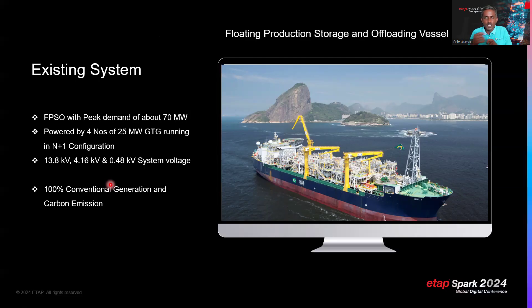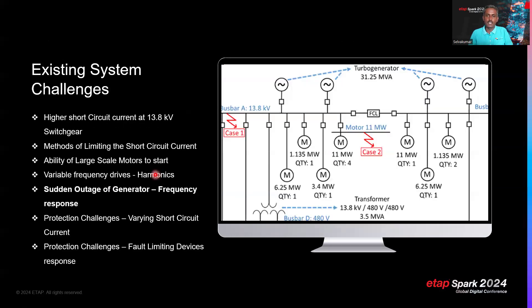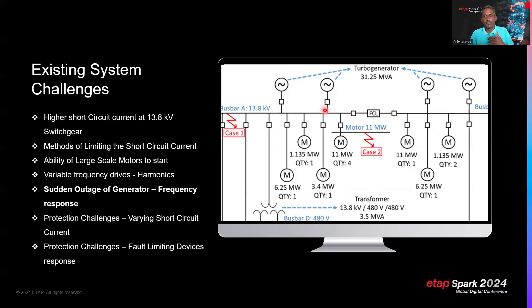Looking in more depth at the existing system: there are four 25-megawatt gas turbine generators at 0.8 power factor, 31.25 MVA, on a 13.8 kV bus. With all generators connected to a common bus and large-capacity motors — including four 11-megawatt and one 6.25-megawatt motor — direct-online starting injects huge short-circuit current. This can push the 13.8 kV switchgear short-circuit level beyond the 50 or 63 kA maximum rating, requiring fault-current limiting solutions.